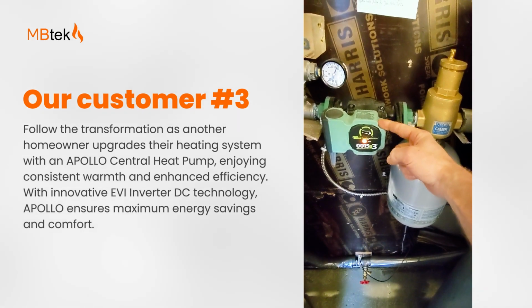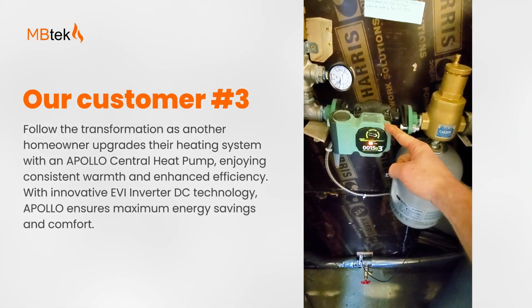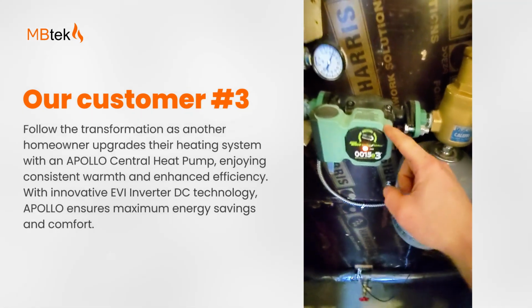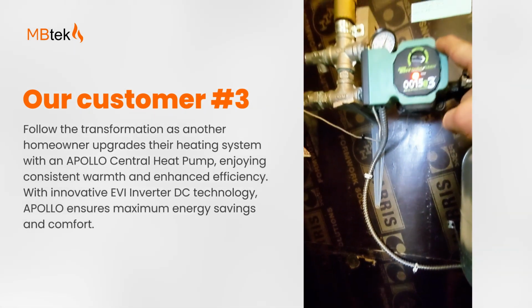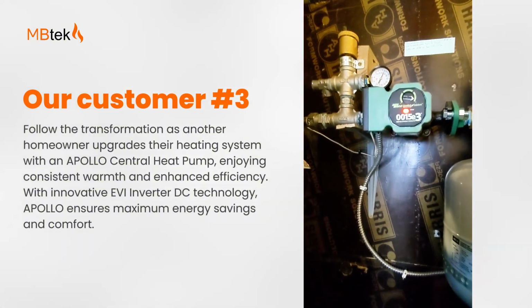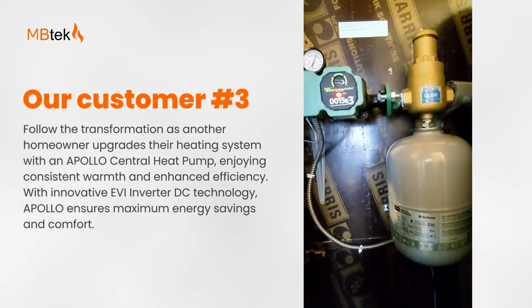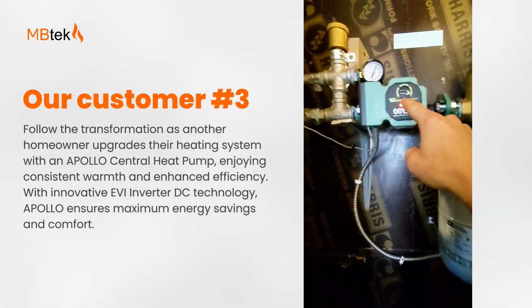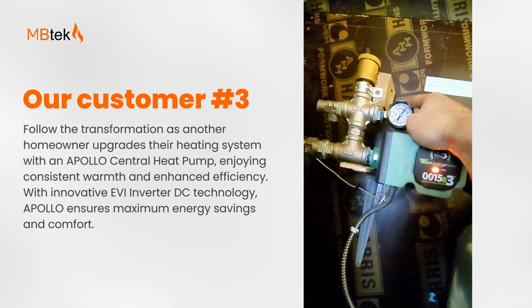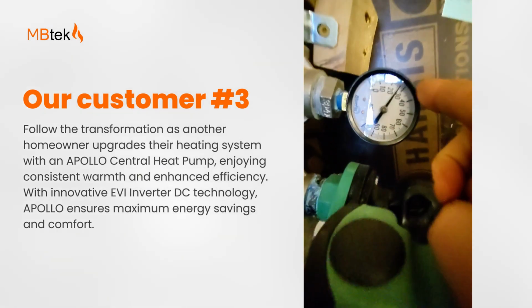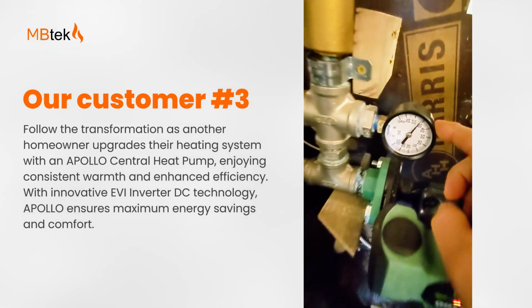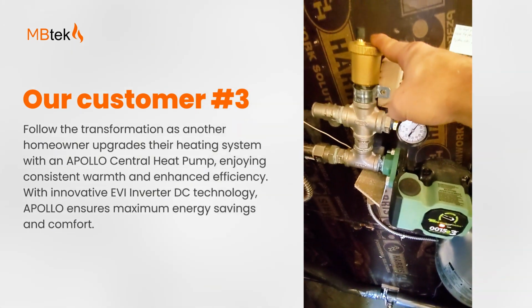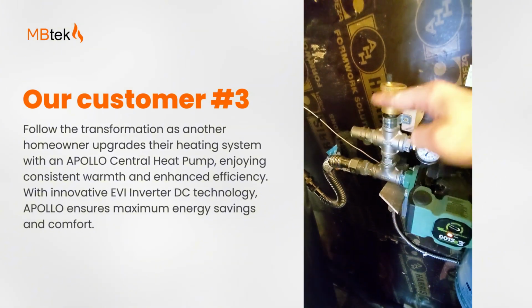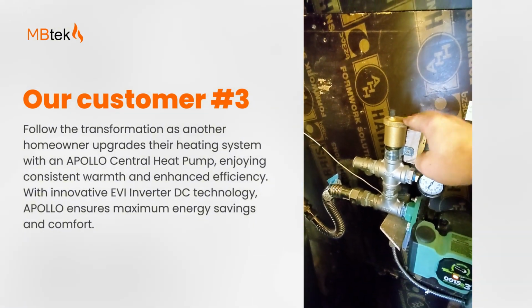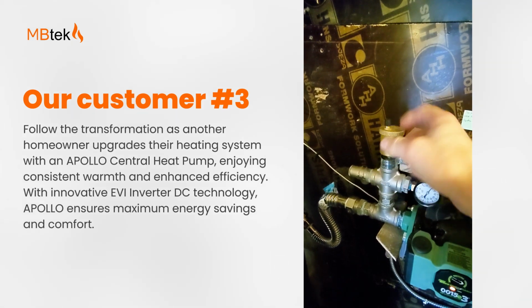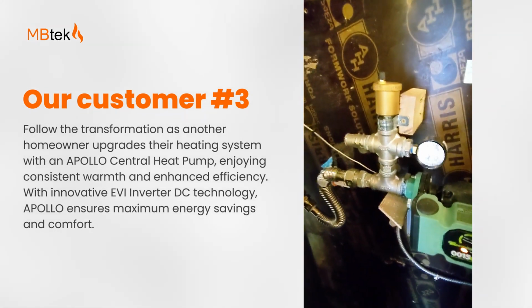Then it goes into the circulator pump, and the circulator pump is moving the fluid around and round between the heat pump and the buffer tank. Then we have a pressure gauge to keep the system pressure monitored, and another air separator valve because it's the highest point in my entire system, so air pockets don't collect in any high spots.